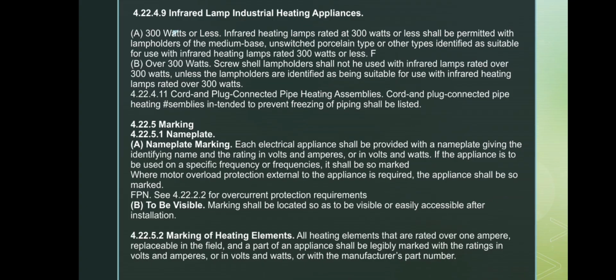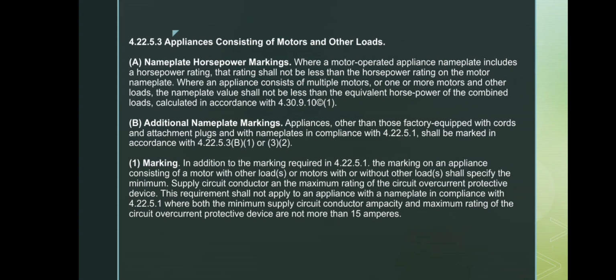Finally, heating elements rated over 1 ampere that can be replaced in the field must be clearly marked with their voltage and ampere or wattage, or with the manufacturer's parts number. Next, we discuss the marking requirements for appliances that contain motors and other electrical loads.